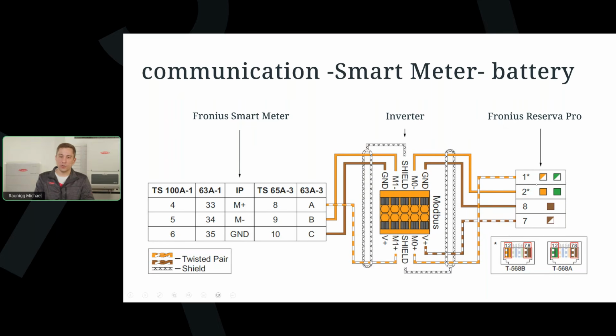And depending on the color coding of type A and B, you need to place them on the Modbus plug of the Gen 24 Plus. So this is our little orange Modbus plug. And of course, like with all the other batteries as well, you need to install Modbus plus, minus, ground, and the plus 12 volt. So these are the four connectors that you need for the battery connection. Please also don't forget to ground the shielding of this CAT cable.